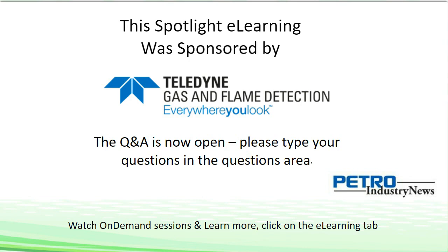And the last thing I would add there is, if in doubt, installing 2 gas detectors for the same gas with 2 different technologies can be one of the best ways around the problem. Because if one of them becomes damaged by cross-contamination, by sensitivities, there is still a chance that the other one might be working. If you're going to install 2 gas detectors with exactly the same technology, there's always a risk that both of them will go down at the same time and you're left with nothing. So if you have the budget and the need to install multiple detectors, it's always worth thinking about different technologies in those detectors, even if you're looking for the same gas.